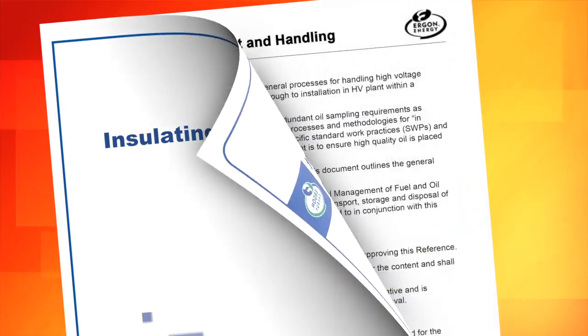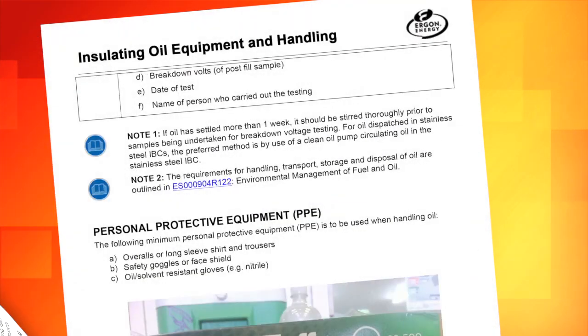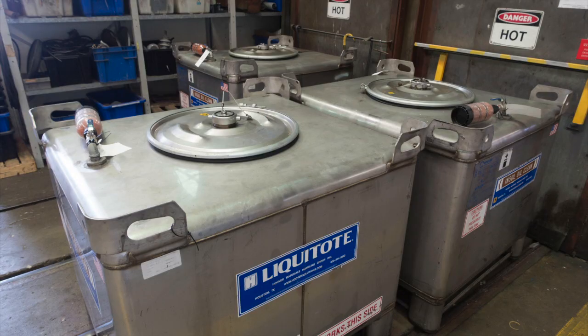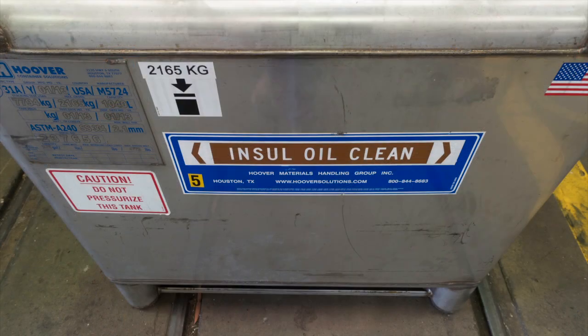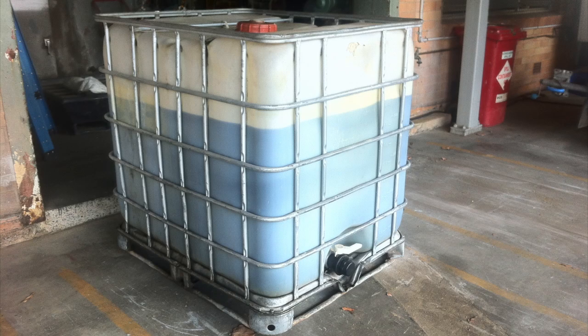And finally, just a few more things to be aware of that are in the standard. We'll be dispatching oil out to the sub-operations staff in stainless steel IBCs. We've migrated away from PVC IBCs for two main reasons. One, we found PVC IBCs are really susceptible to sweating, condensation, which significantly affects the breakdown voltage of the oil. And secondly, just from an environmental perspective, they are more susceptible to damage.